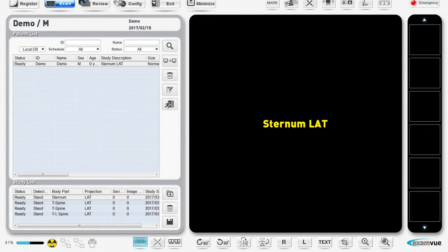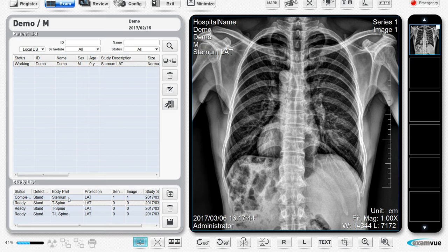The patient list will have all the patients you are registered but have not been finished taking x-rays on. It will automatically select the first view on the study list so you can take the first x-ray. Position the patient and take the exposure. After the image is acquired, the software will automatically move to the next scheduled x-ray. If you follow the scheduled exam, you will not have to touch anything in the software until the exam is complete.